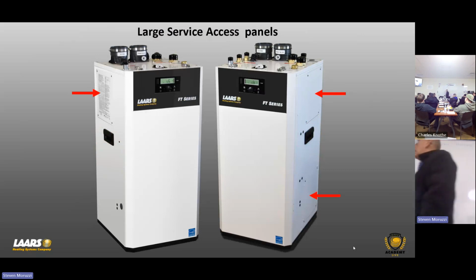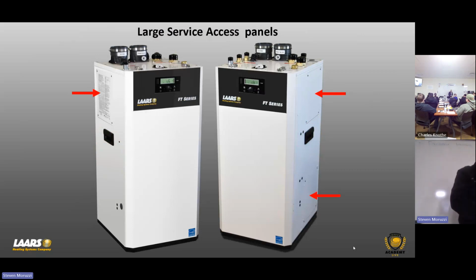If you are not putting a condensate pump in the cabinet, which a lot of guys in a larger basement want to leave external, right, outside so they can clean it or get to it, elevate that boiler up on pads. Why? Because we have a built-in condensate trap inside the cabinet. And what happens is where you're going to come out, it comes out on the bottom, and then you have to take it up into the condensate pump. So you're double trapping it. So just elevate that if you're using an external pump. Does that make sense? And there's also leveling legs.